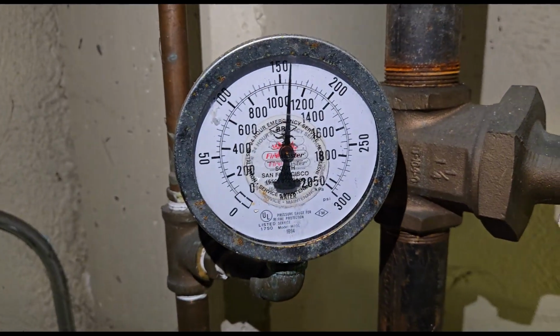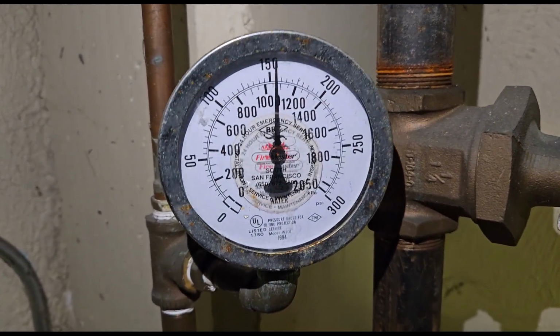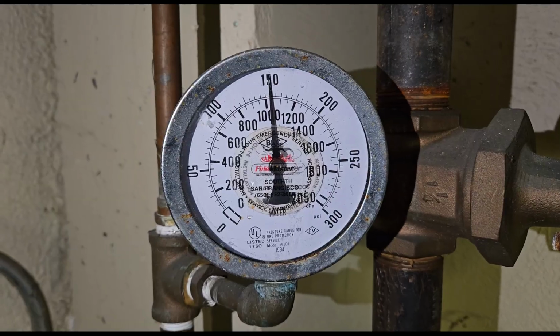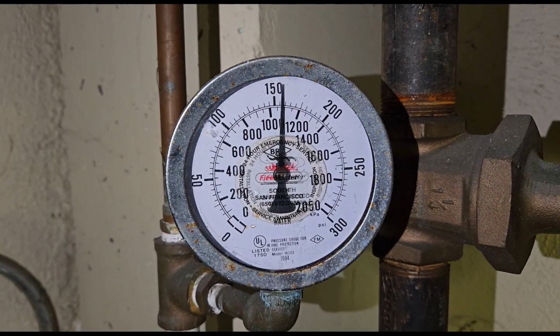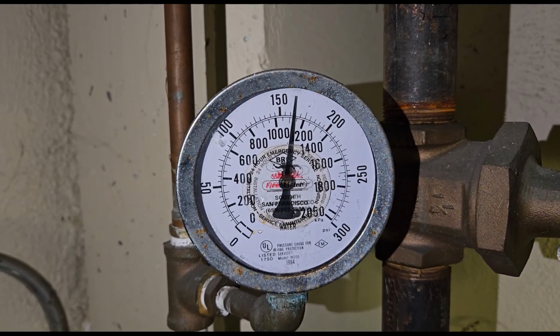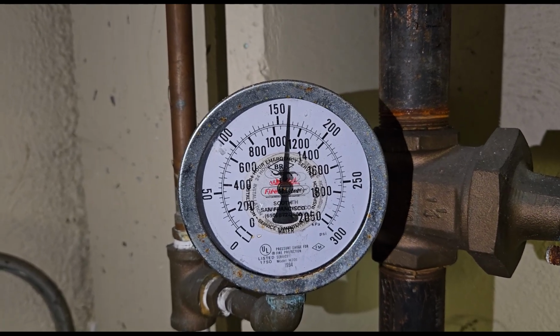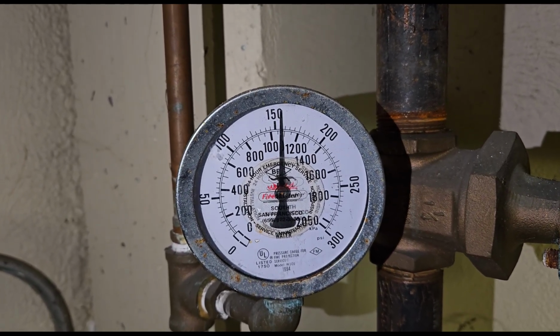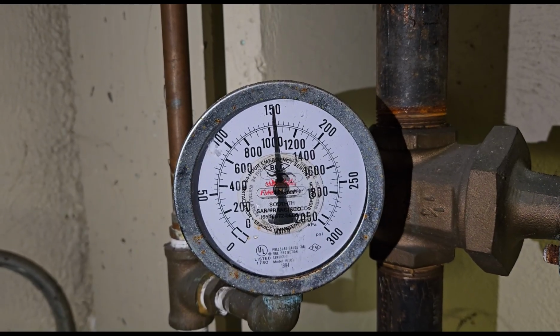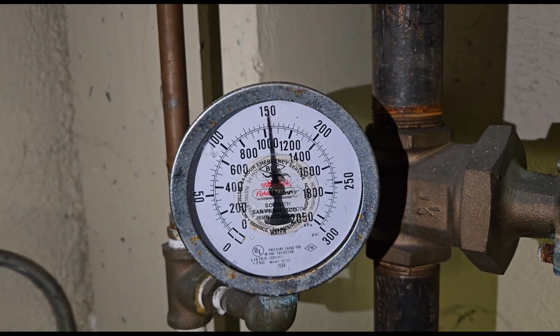Get a close-up of the gauge. So as you see the pressure dropping below that 150, it's gonna kick on. And just like that, all right, and it'll drop back down. Again, this is just the jockey pump maintaining pressure as the water's flowing.